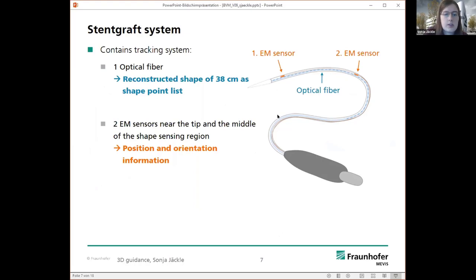And also we have integrated two EM sensors. One is at the tip and one at the middle. And this allows us to obtain the position and orientation information for both EM sensors. And since we placed both EM sensors at the front, it allows an accurate localization at the front part of the stent graft system.